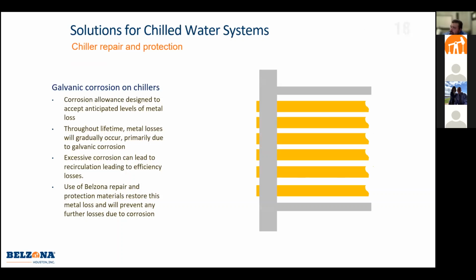And we'll go on down the stream to the chillers that everybody uses. These chillers are typically made with a lot of corrosion allowance on the tube sheets, but eventually you reach the point where you either have to replace it, which can cost an extreme amount of money, or you can use us to come in. We can rebuild that metal loss and give you an erosion resistant ceramic coating on it.